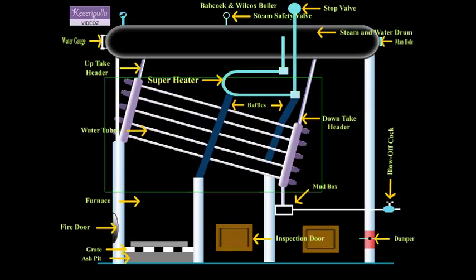Water Tubes: A large number of water tubes are connected between the uptake and downtake headers. The water tubes are situated between the drum and the furnace. The water tubes are inclined at 5 degree to 15 degree angle to increase the water circulation. The water tubes are about 10 cm in diameter.